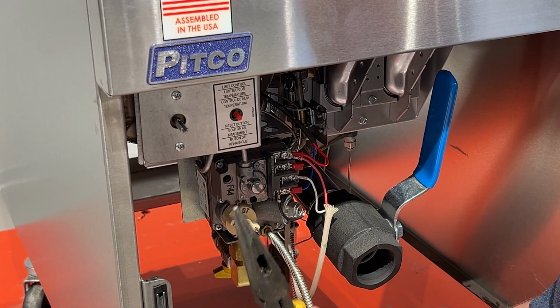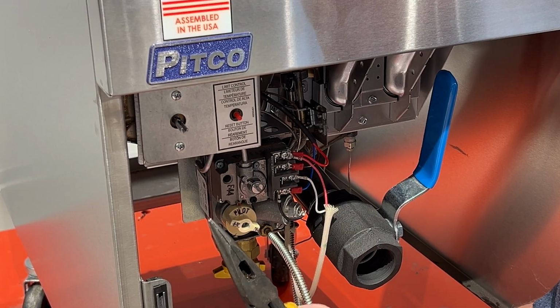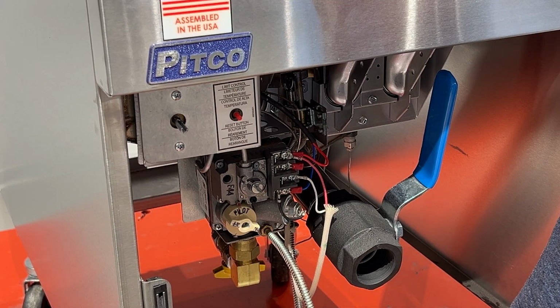Since the oil was 30 degrees hotter than our set point, we need to bring the set point up to that temperature. In order to calibrate up, we have to turn the calibration screw counterclockwise.